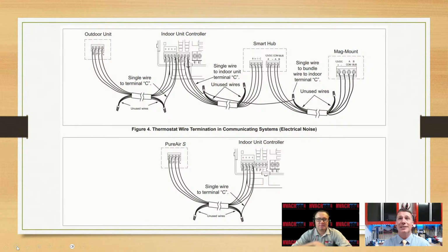All right. Let's start at the indoor unit, Todd. Interesting that everything's tied back to the indoor unit on these unitary systems. It'll be completely opposite when we get to our ductless. Ductless, absolutely. But all of our unitary, our primary DC voltage is coming from that indoor control board. So let's look at this indoor control board. This one's using a smart hub because it's connecting another component to it, but we can even talk about the smart hub if we needed to.